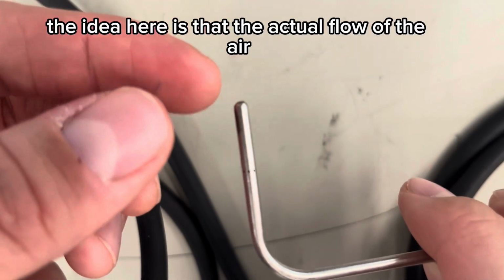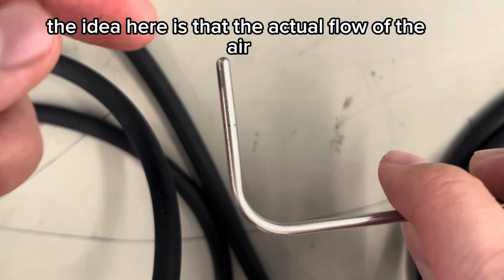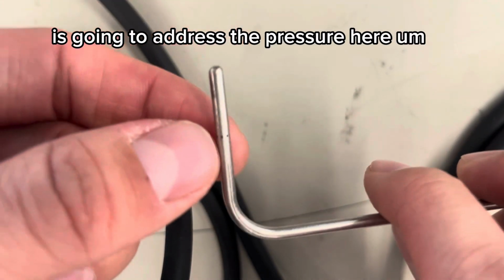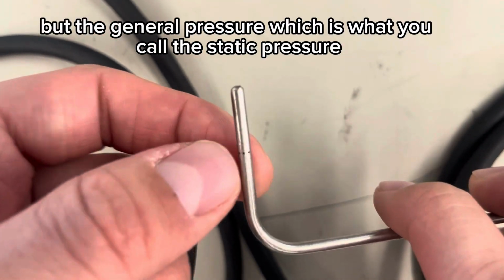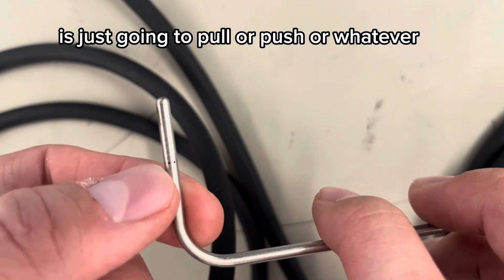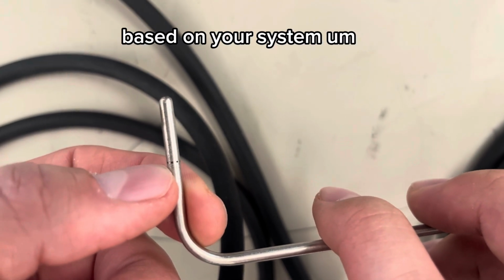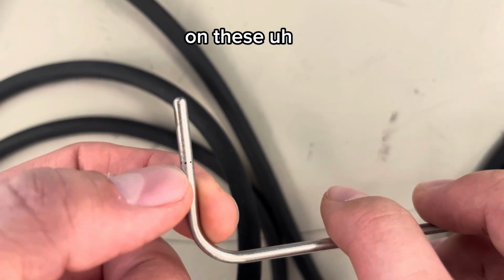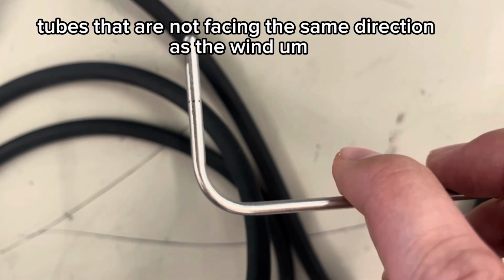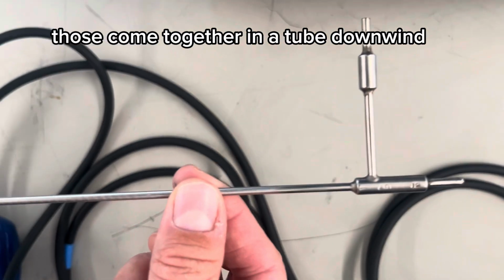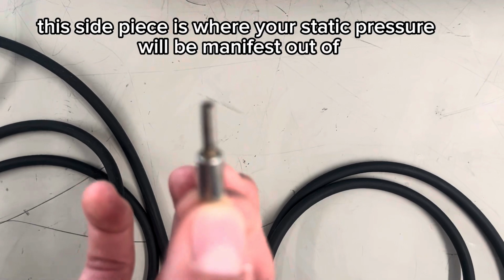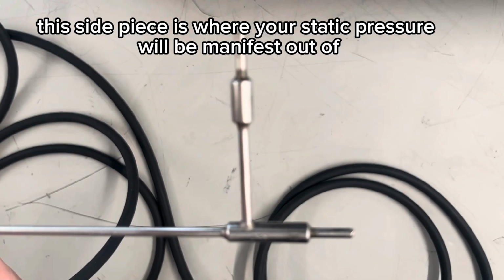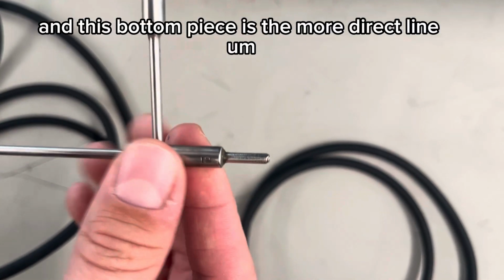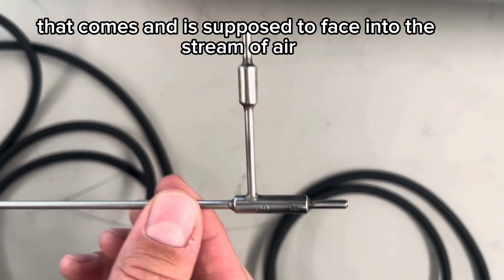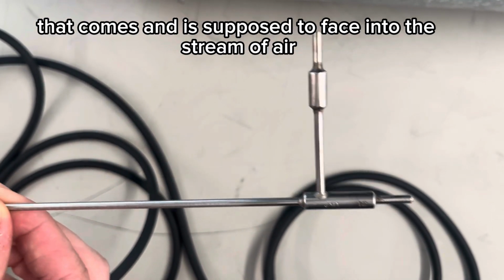The actual flow of the air is going to address the pressure here, but the general pressure, which is what you call the static pressure, is just going to pull or push based on your system on these tubes that are not facing the same direction as the wind. Those come together in a tube downwind. This side piece is where your static pressure will be manifest out of, and this bottom piece is the more direct line that is supposed to face into the stream of air.